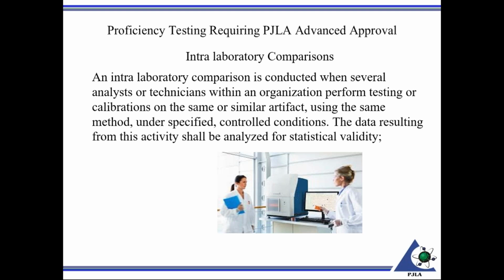All right, going down the pecking order. We mentioned intra-lab comparison. Just bear in mind, this will require approval from PJLA in advance. An intra-lab comparison is conducted when several analysts or technicians within an organization perform testing or calibration on the same or similar artifact using the same method under specified control conditions. The data resulting from this activity shall be analyzed for statistical validity.